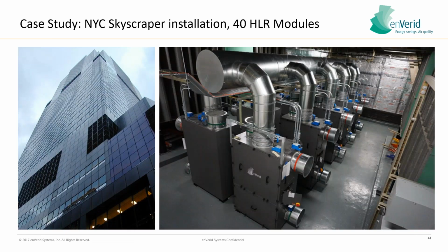Here's a picture of that installation. You can see that we were actually installed within a mechanical room, which is also a plenum, which is why the inlets to the unit are unducted. You can see the large fan wall there off in the upper left-hand corner of the photo to the right. And then that singular duct at the top of the screen is for the regeneration process.